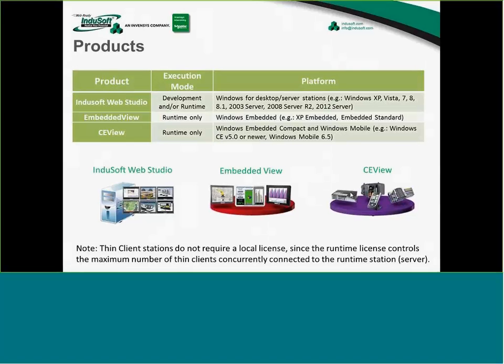The embedded view is a very small footprint version of the InduSoft Web Studio runtime. It doesn't have all features. There are some limited capabilities there, but it's very robust. I mean, it has a lot of what you get in the full PC version. But it's, of course, a lot cheaper, and it's limited to 4,000 tags. The biggest limitation is that you can only use 4,000 tags.